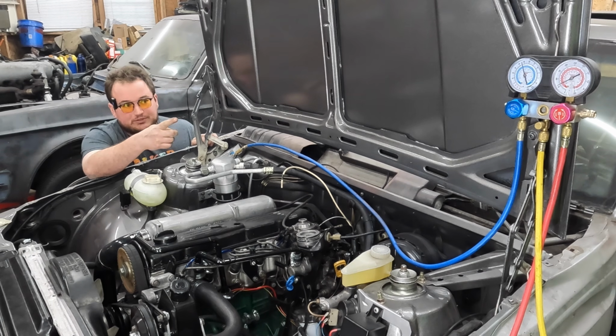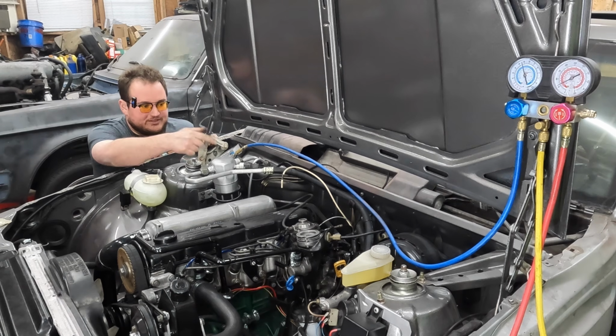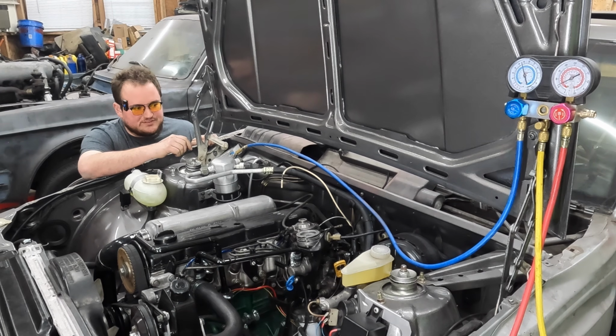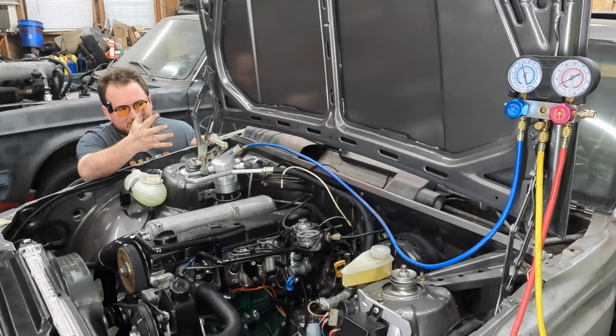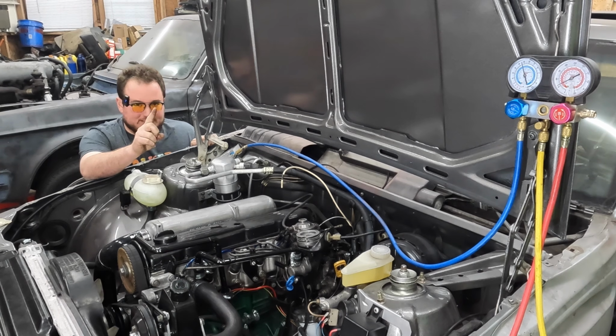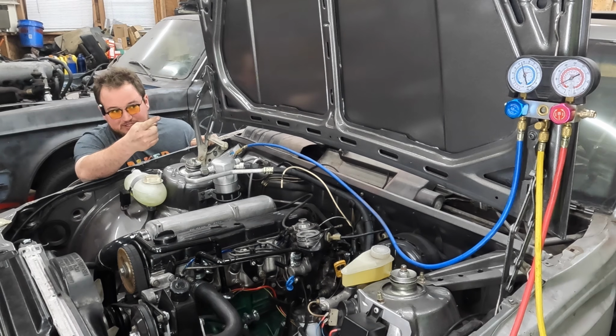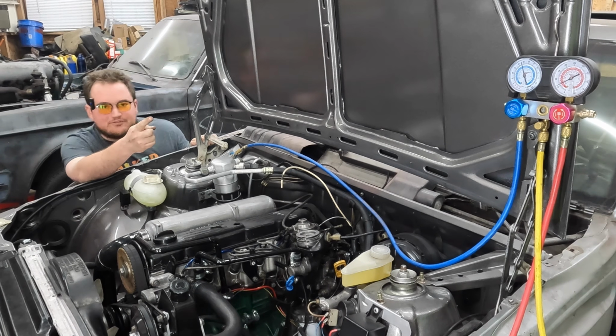Since it's cold, the compressor discharge pressure only got up to maybe 120, but that was still plenty to drop the low side down low enough to cut that switch off and cycle the system. I said this refrigerant is about 70 psi at room temperature, but I'd like to clarify it is not currently room temperature. So when I started it was maybe 50 psi. Can't read them from here.